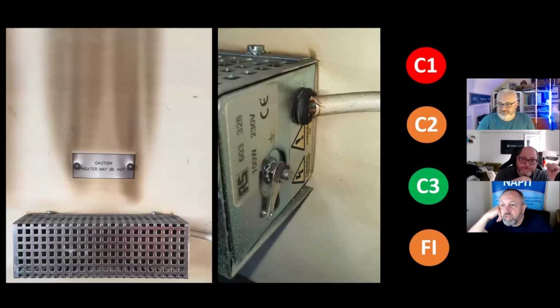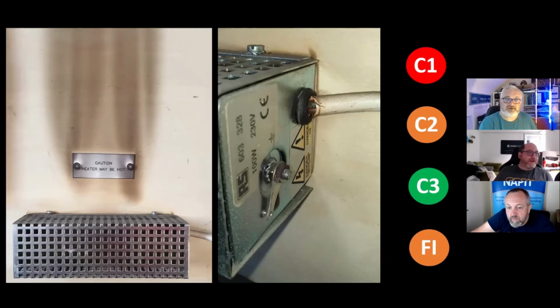I think the size of the heater is irrelevant. If it's a small confined space, it's going to get hot in there. So let's agree C1, maybe C2, with regards to the containment and limited access, which means we acknowledge the C2s in chat. I'd happily agree with the C2 because it's within a metal enclosure. Feeder pillars are generally metal enclosures, which generally contain. I've worked with some wooden ones, there's still some around. Oh no, that's just ply lined though, so that bit would burn, but hopefully it would contain it.